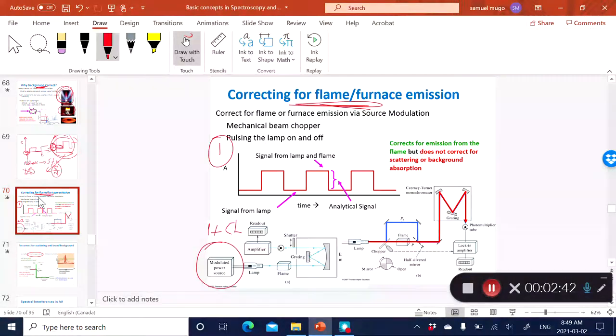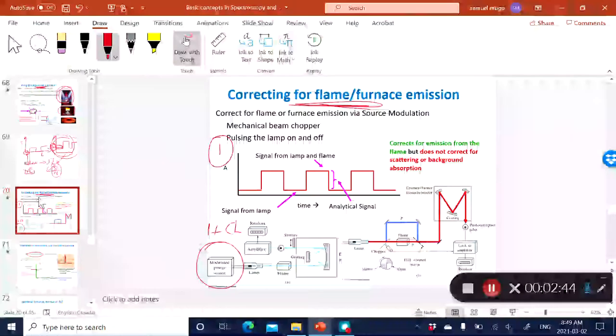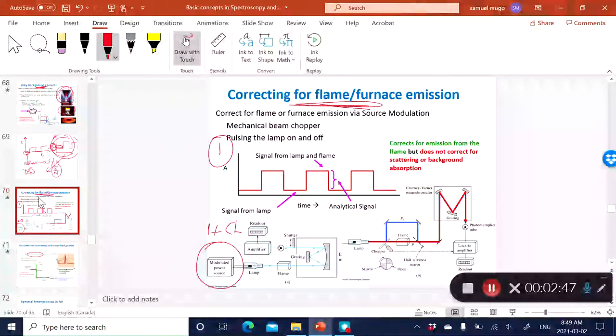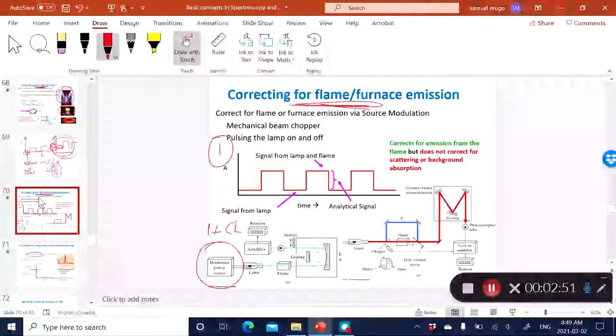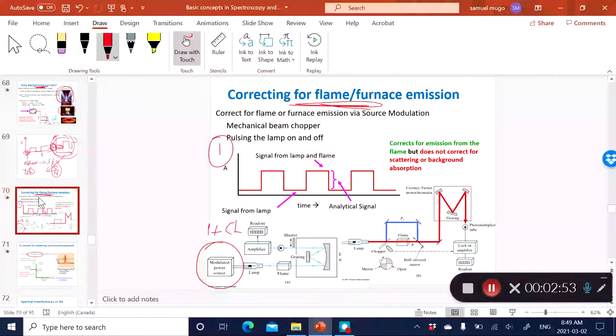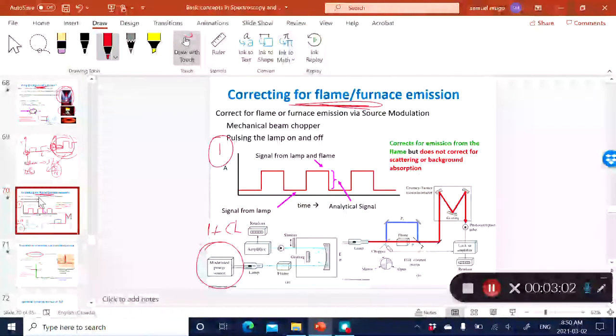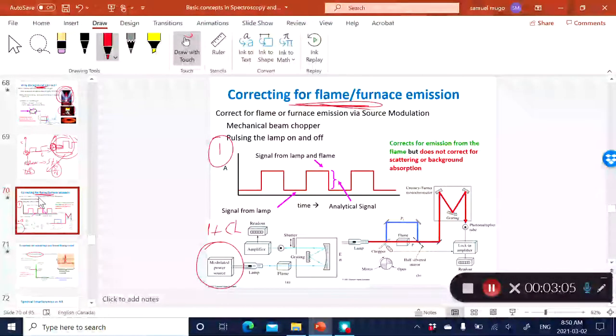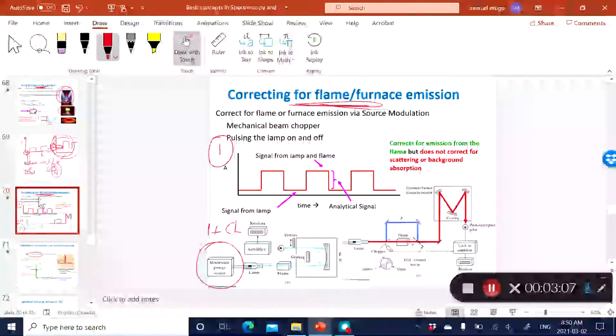When the lamp is on, you're detecting both the matrix or background as well as the analyte signal. While it's off, you're only detecting the background. When you subtract the two, you're only going to get your analyte signal.